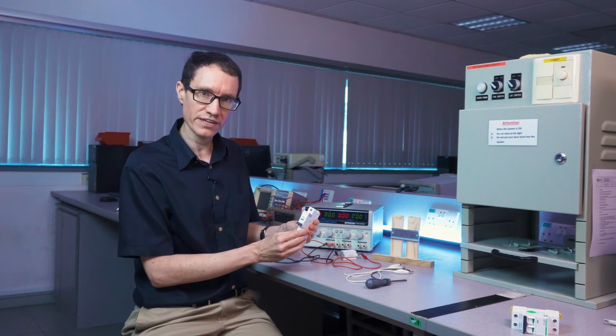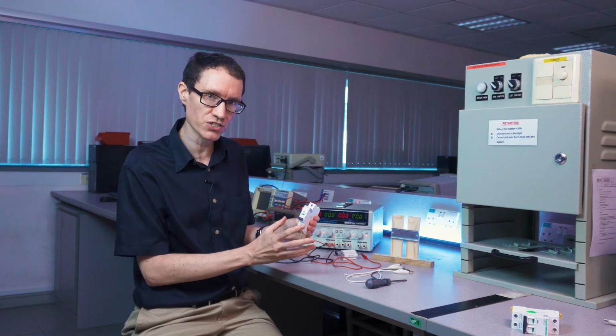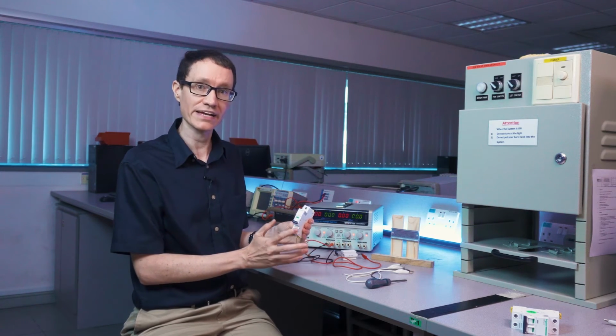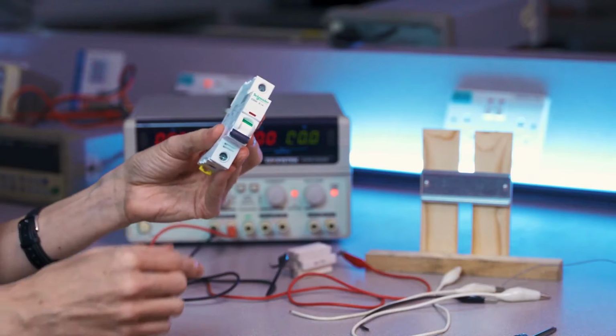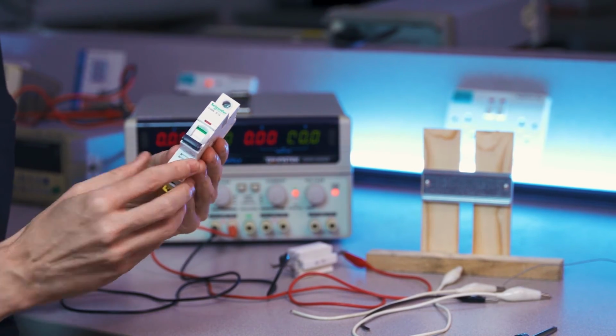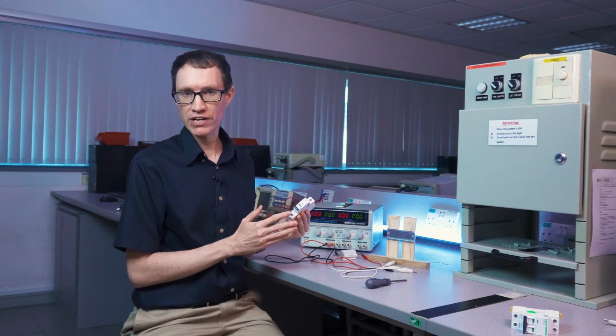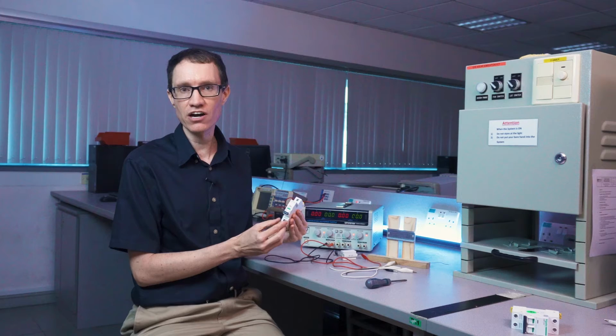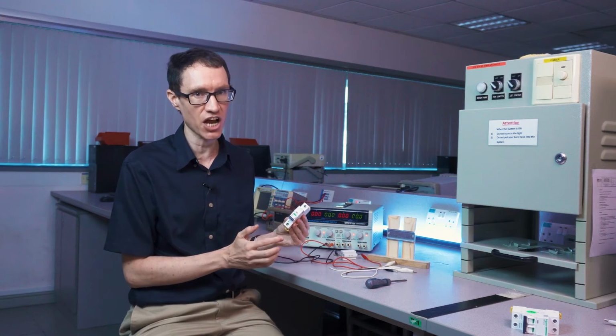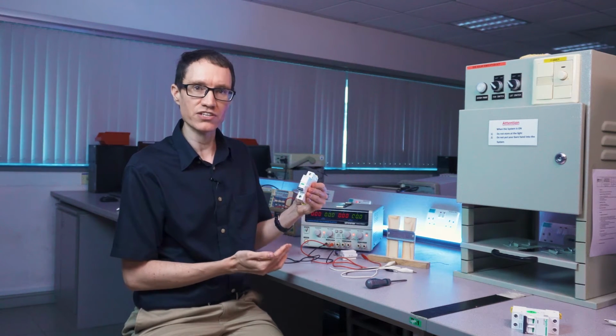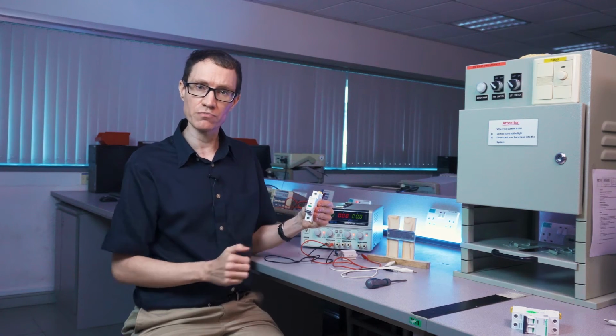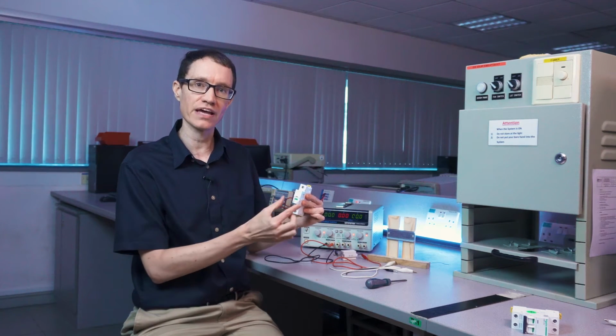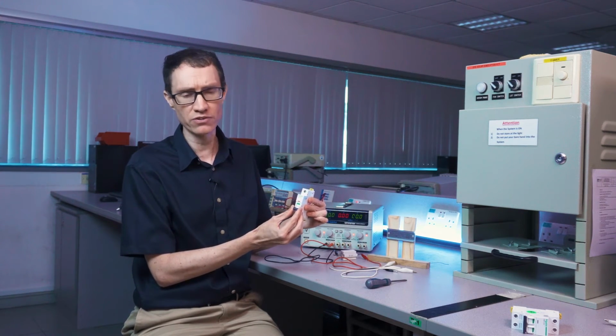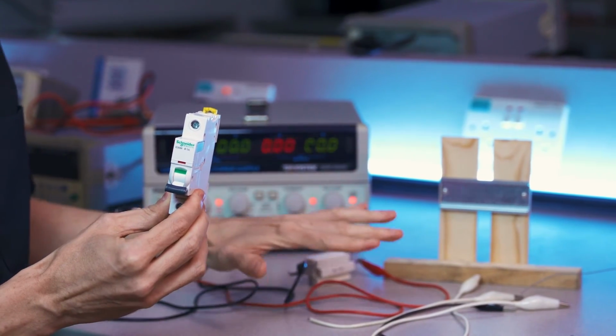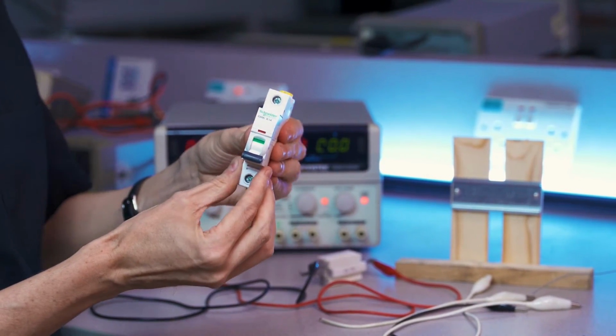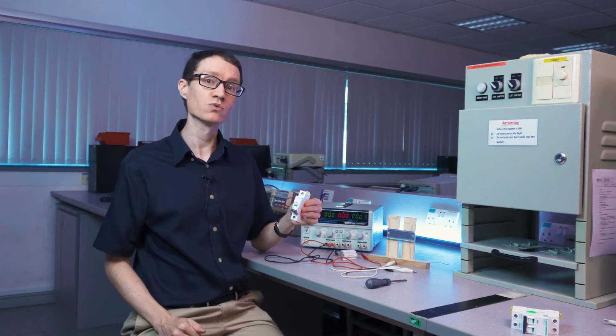The circuit breaker, again, doesn't care so much about the voltage across the circuit breaker. It cares more about the current going through it. When circuit breakers are actually installed, the main purpose of the circuit breaker is to protect the wiring. It's to guard against fires. It's not to guard against shocks. So the wires that feed into and out of a circuit breaker have to be matched in order to handle the current that the circuit breaker is rated at. The wiring that I have here in front of me can handle 1 ampere of current, so we're okay when it comes to wire gauge.